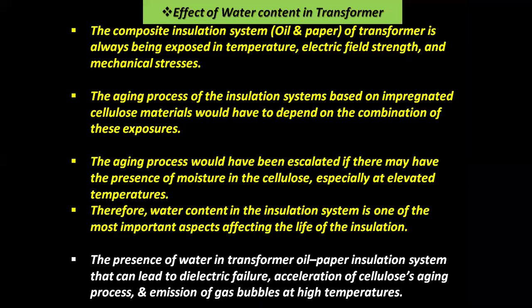Now, the effect of water content in a transformer. The composite insulation system, oil and paper, of a transformer is always exposed to temperature, electric field strength and mechanical stresses. The aging process of insulation systems based on impregnated cellulose materials depends on the combination of these exposures.